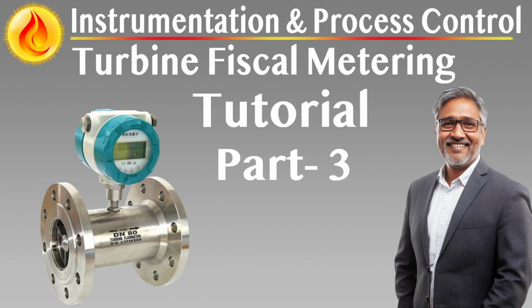Strainers, debris protection and flow assurance for measurement integrity. Strainers are essential upstream components in each metering run, serving to protect the turbine meter from mechanical damage caused by particulate matter, corrosion products, or pipeline debris. Each metering stream must include a single basket strainer constructed from stainless steel, equipped with a removable mesh insert matched to the particle size tolerance specified by the turbine meter manufacturer.